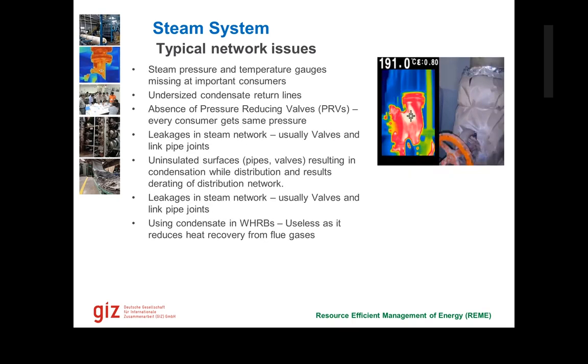Then obviously, we are all aware of the losses because of uninsulated lines, because of leakages, because of absence of pressure reducing valves. These are the points that we need to look at generally. And then I saw that some companies use condensate in the waste heat recovery boilers. It actually reduces the waste heat recovery rate. So feed fresh water to waste heat recovery boilers and feed the condensate to actual boilers. That is what we should do usually.